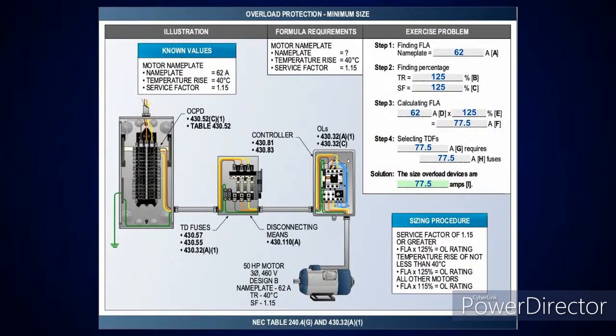All right? And then when I get in and I start doing my overload protection, one of the things I told you is go look at 430.6A2, and it tells you when you're doing your overload protection to use the nameplate value. Now there's 3 items I need to look at here. I don't even really care what size motor is or what voltage it is. I want to know the nameplate, I want to know the temperature rise, and I want to know the service factor. That's it. Right.